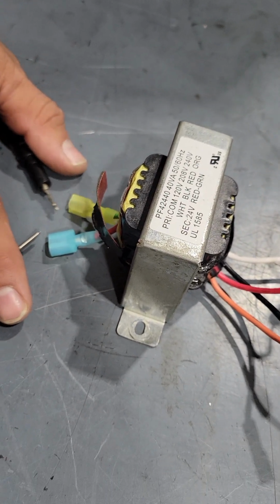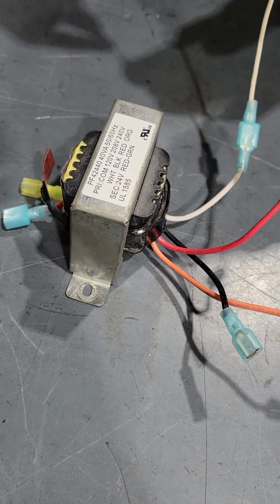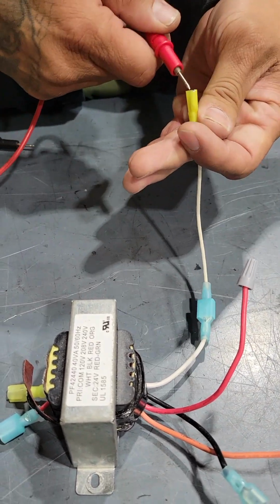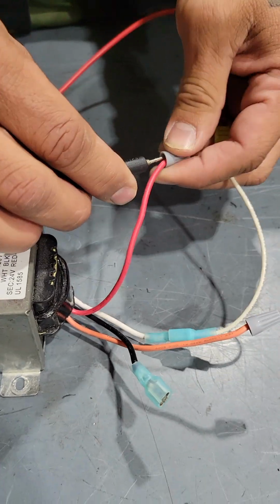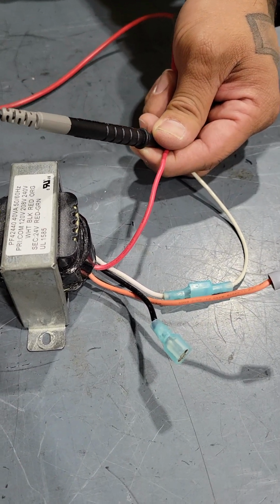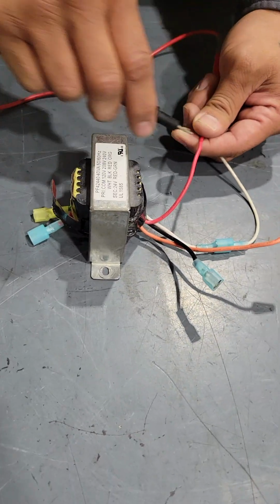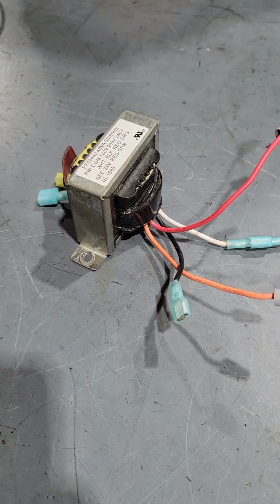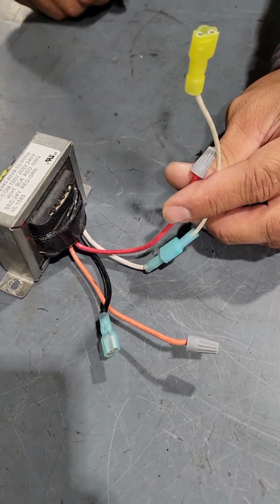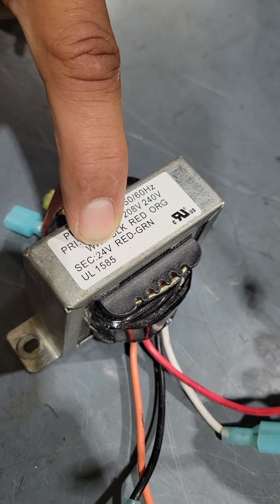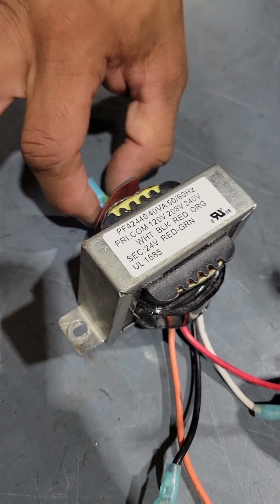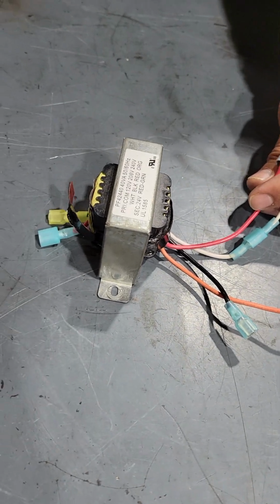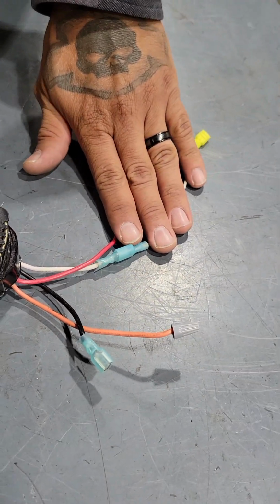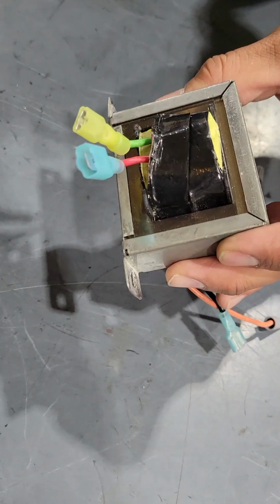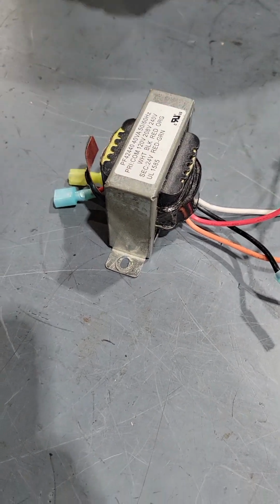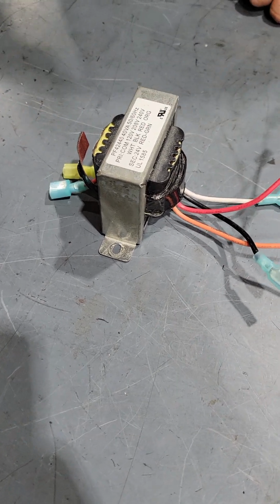So the first thing you should do is ask, do I have the correct voltage coming in to my component? All right, and we're measuring and we see 208 volts, and that's exactly what we need to see. That's perfect. We know that our transformer is bad because we have the required voltage, 208, to make the result we need, but we're only getting 12 volts. That's half of what we should have, but we have the full line voltage coming in. That lets you know your transformer is bad. There is no fixing that. It's only replacing it. That's the only thing you can do to that. And that's it.